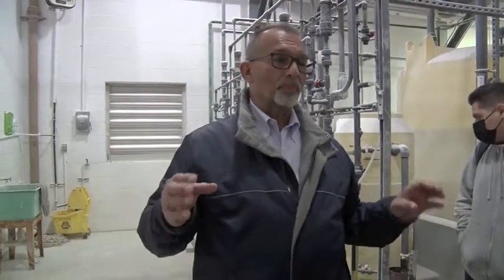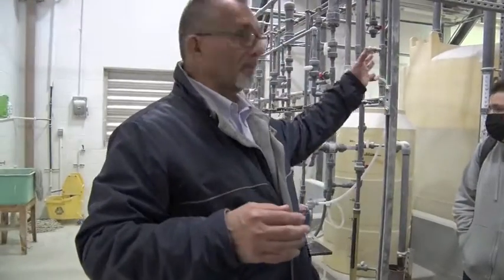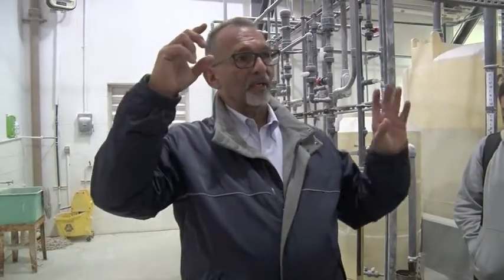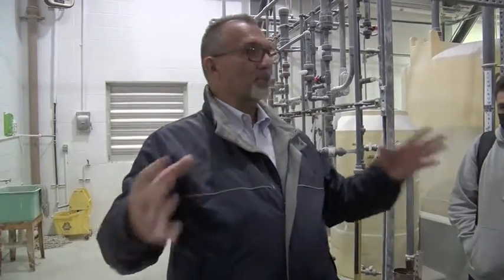The pH of the water here is very low. It's about 4. We really need a pH of 7 to make the water potable. But by adding lime, we can increase the pH of the water, and that will help us in the process of the treatment. So we're going to go upstairs and we'll show you what each chemical does and how much we add to the water, okay?